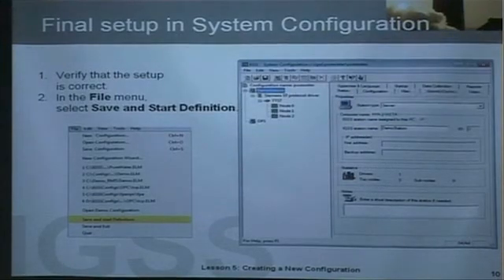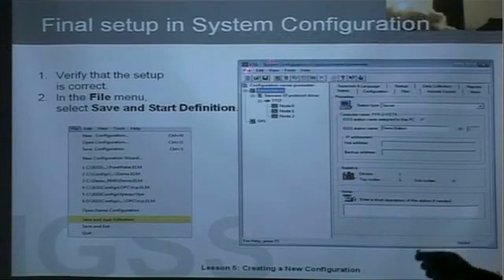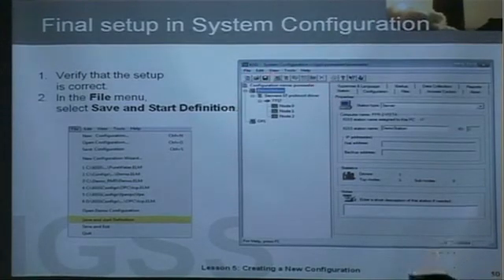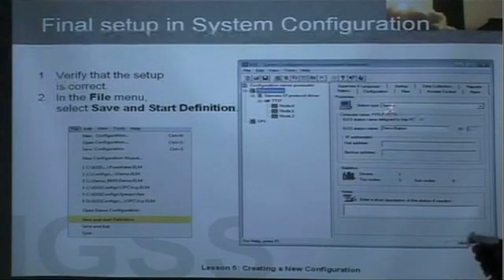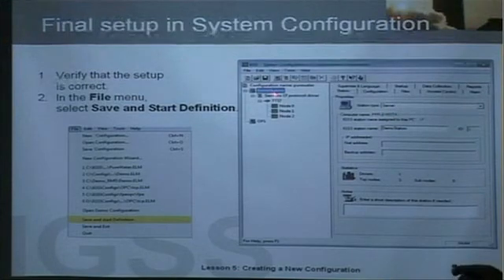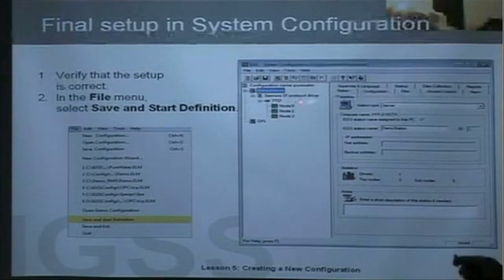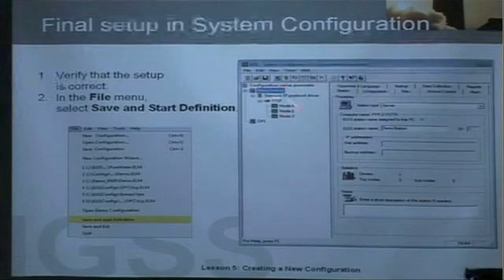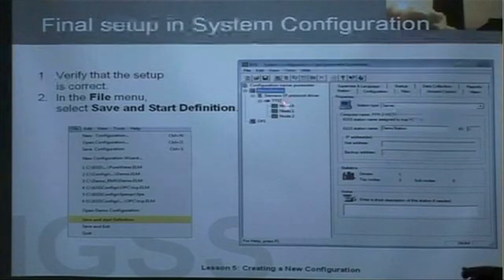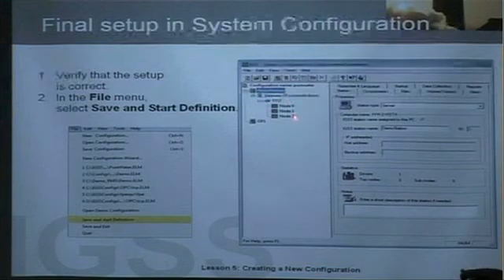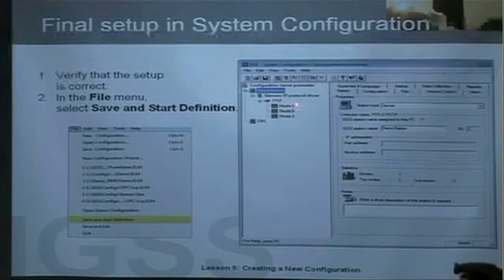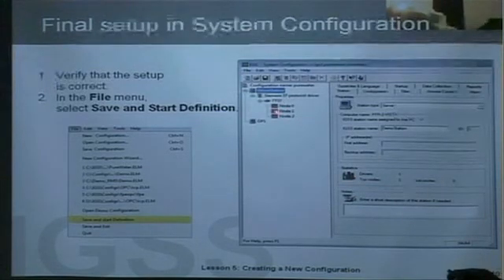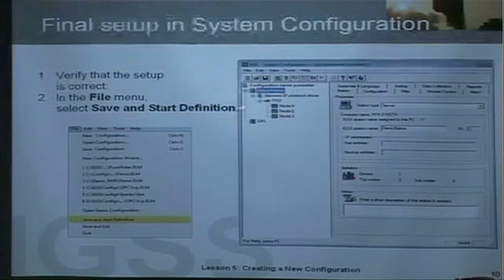When all this is done, we will see a tree structure in system configuration showing exactly what we've set up in the wizard. We set up the demo station as our server, we set up the Siemens S7 driver, and underneath the S7 driver we have specified three different nodes or PLCs. A node in IGSS is a PLC, and each PLC has a unique number — 0, 1, and 2. Finally, we specified our operator station which was called OP1.